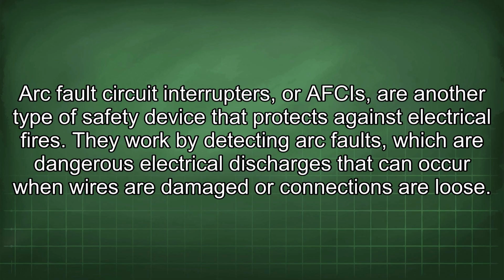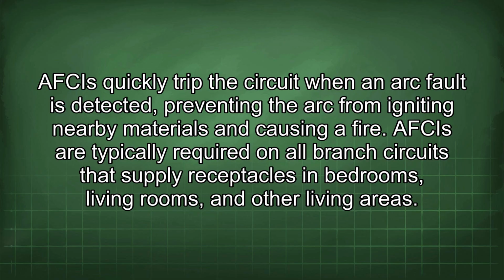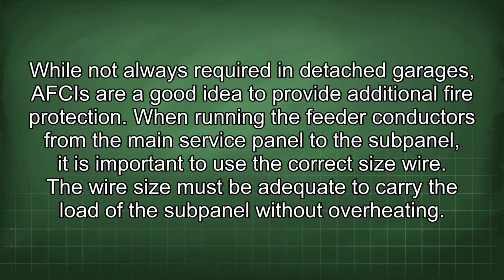Arc fault circuit interrupters, or AFCIs, are another type of safety device that protects against electrical fires. They work by detecting arc faults, which are dangerous electrical discharges that can occur when wires are damaged or connections are loose. AFCIs quickly trip the circuit when an arc fault is detected, preventing the arc from igniting nearby materials and causing a fire. AFCIs are typically required on all branch circuits that supply receptacles in bedrooms, living rooms, and other living areas. While not always required in detached garages, AFCIs are a good idea to provide additional fire protection.